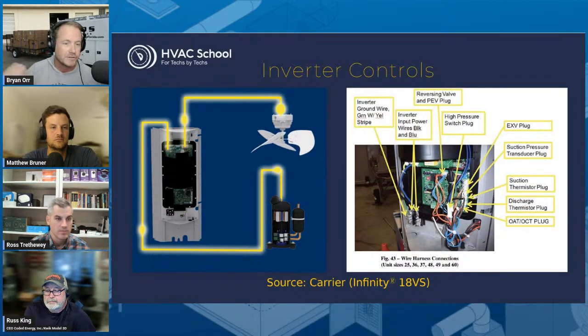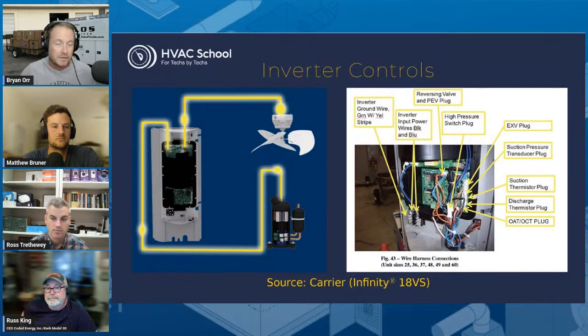And for anybody who works in refrigeration, you know the impact this has, because you're still rejecting heat to an indoor space that's hopefully about the same temperature as it was before. What that results in is a much higher compression ratio. When you have a higher compression ratio, your output decreases. In your granddaddy's heat pump, you just produced less heat as it got colder outside, as your compression ratio increased. One of the main reasons for that, to what Matt is saying, is that your mass flow rate decreases. Your suction gas coming back to your compressor is lighter. If you have lower pressure, it's lighter gas coming back to the compressor. So every time that compressor spins or every time that piston pumps, it moves less because the mass is less. You're moving the same volume in the chamber, but the mass is less.